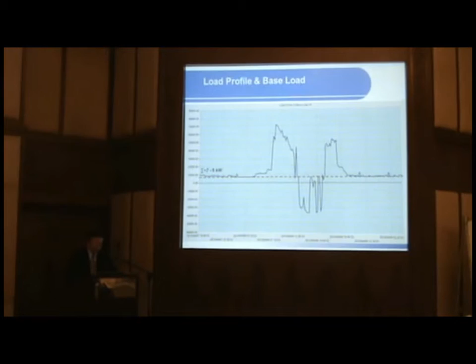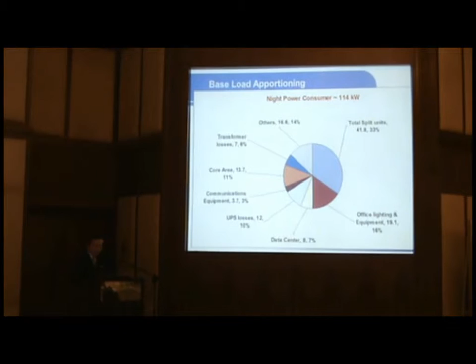When a building has a high base load, for example one building in Cyberjaya at 114 kilowatts, what is inside there? At night we did the energy audit and a lot of washing through the data. The majority comes from split units that cool down the ICT equipment, servers, telco, hub switches, communications, and so on, and also transformers.